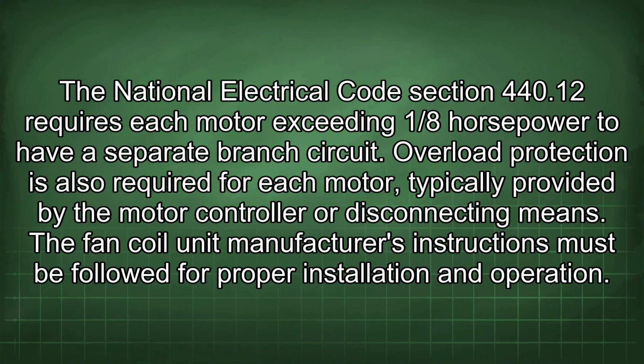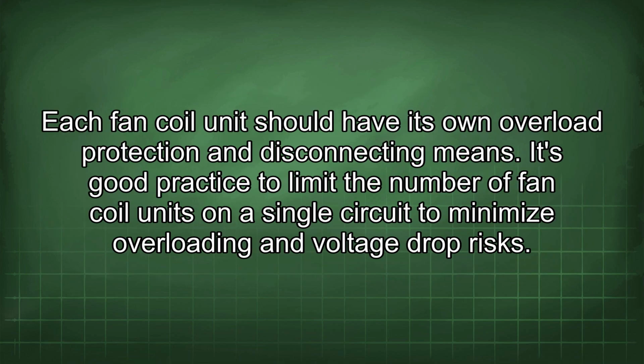The National Electrical Code Section 440.12 requires each motor exceeding 1/8 horsepower to have a separate branch circuit. Overload protection is also required for each motor, typically provided by the motor controller or disconnecting means. The fan coil unit manufacturer's instructions must be followed for proper installation and operation. Each fan coil unit should have its own overload protection and disconnecting means.